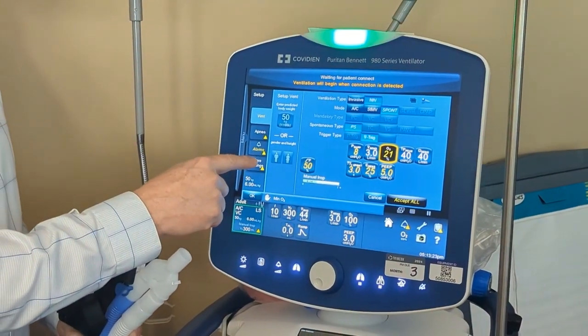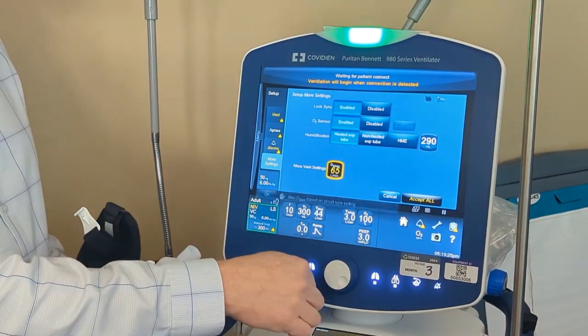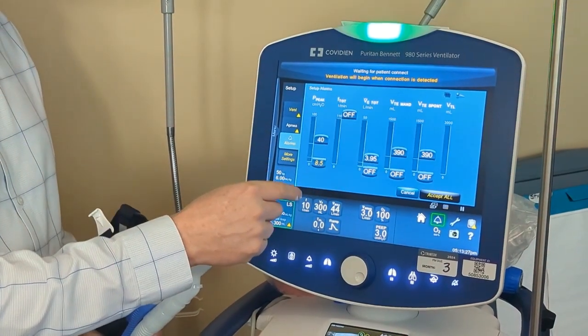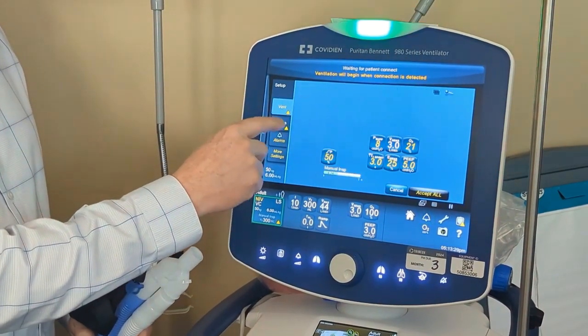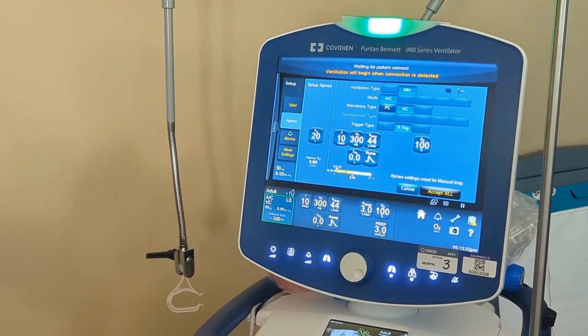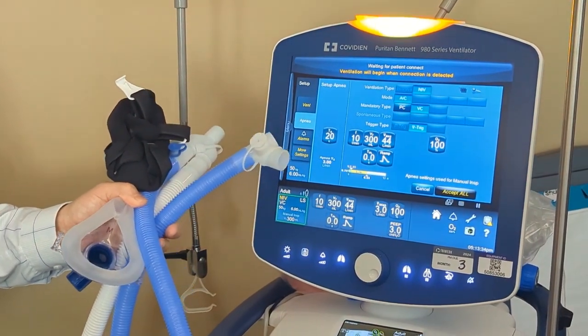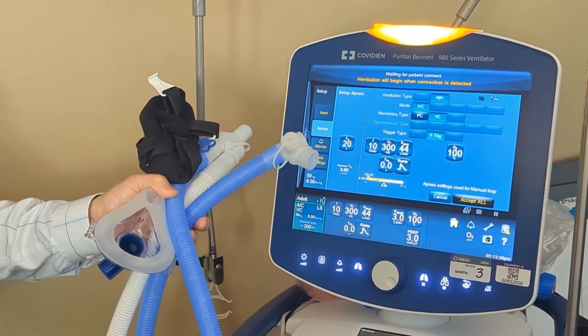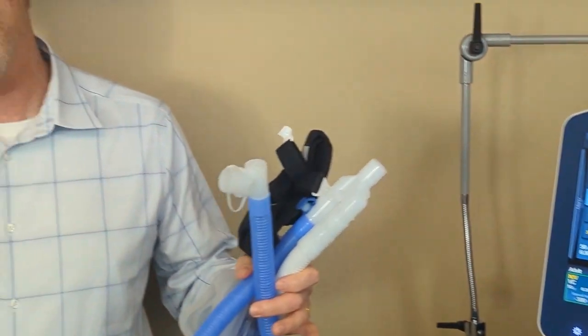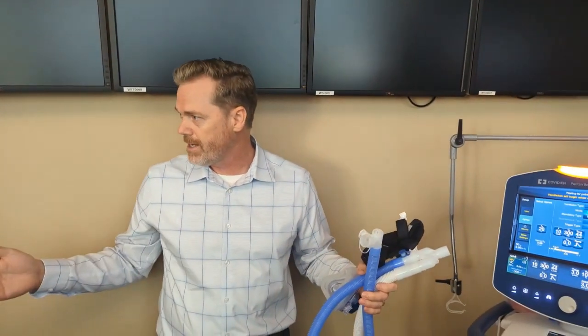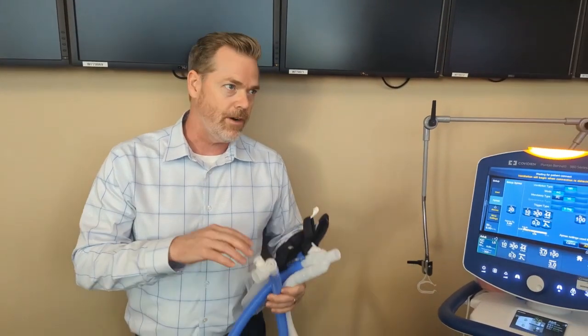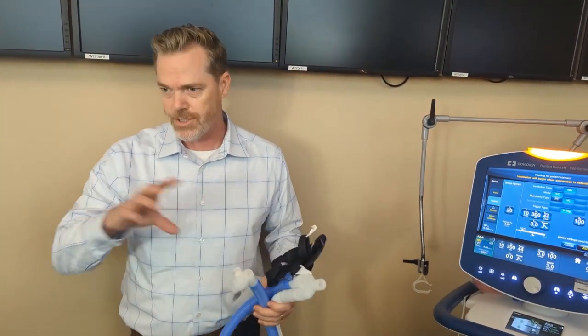Now, remember how I talked about alarm history earlier? So if I want to go in, let's see, for however long it's on the patient, the only way you can clear your apnea, then of course we can go and set all that kind of stuff up, but that's going to be very similar. Another added benefit of the V60: we had to put a backup rate in because it did backup rates and apnea stuff differently than an invasive ventilator did. So here we can just put our apnea settings in.